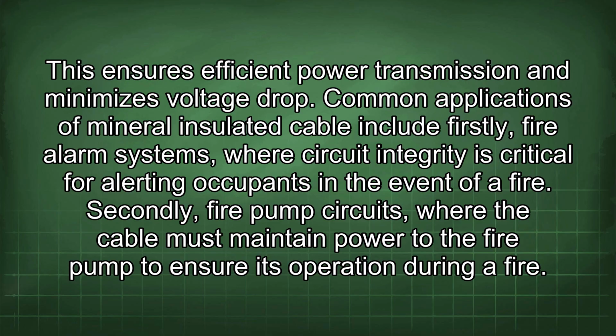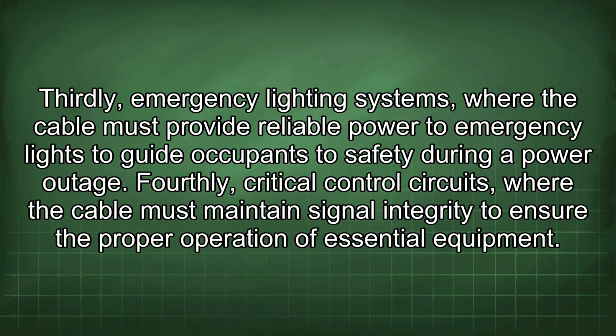Common applications of mineral-insulated cable include, firstly, fire alarm systems, where circuit integrity is critical for alerting occupants in the event of a fire. Secondly, fire pump circuits, where the cable must maintain power to the fire pump to ensure its operation during a fire. Thirdly, emergency lighting systems, where the cable must provide reliable power to emergency lights to guide occupants to safety during a power outage.